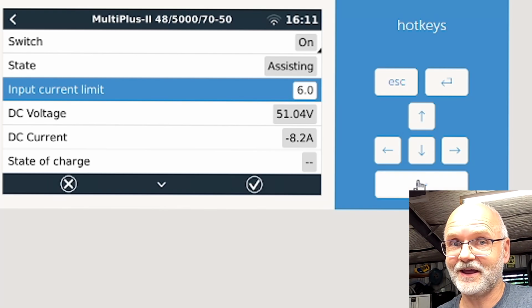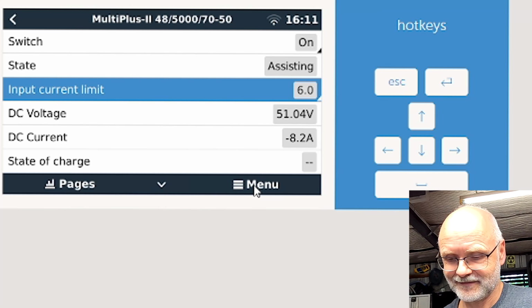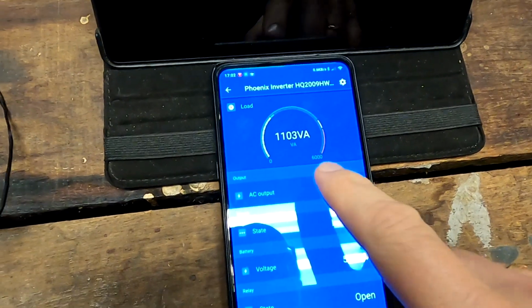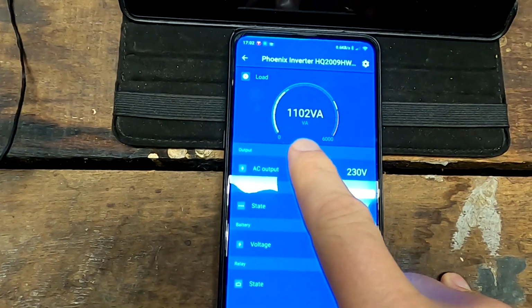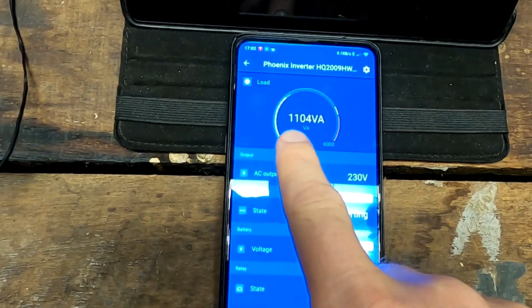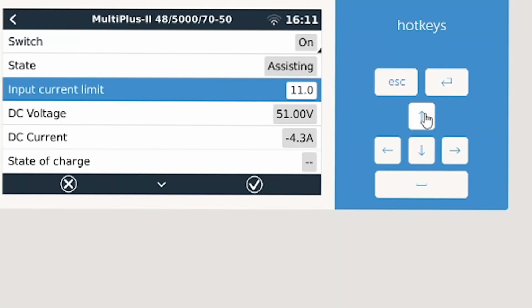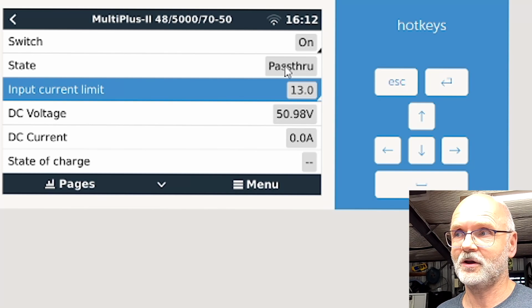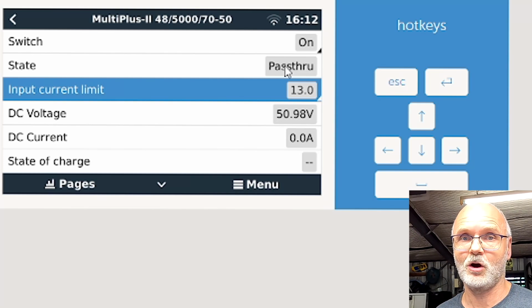Okay, then let's set it to 10 amps, because in reality it would sit on 10 amps, right? At least. And now we can see here, this is the Phoenix inverter. Okay, let's crank this up to 13 and see. Yep, that works. See, the state went from assisting to pass-through, and now only the Phoenix inverter is delivering all the power to our load.